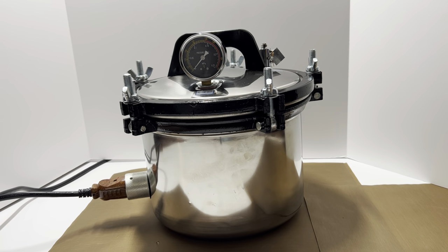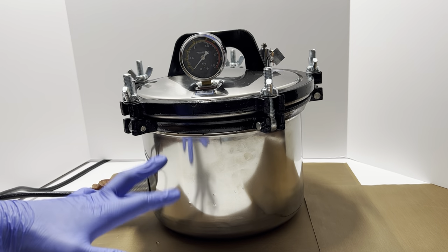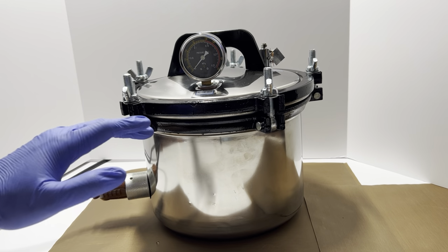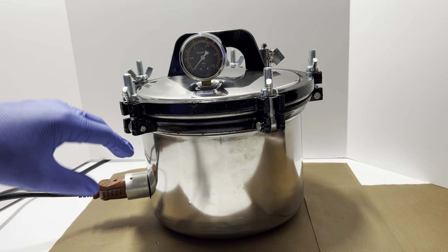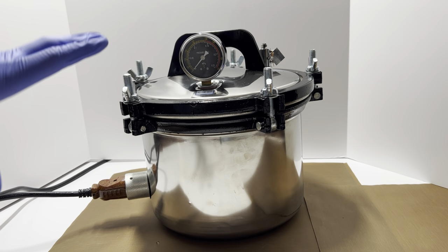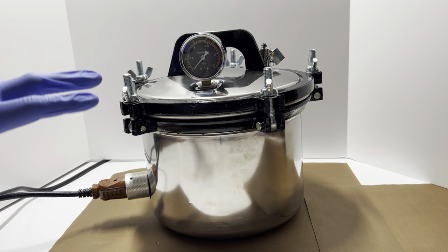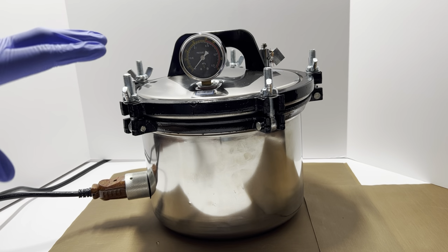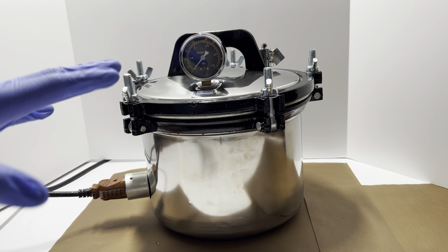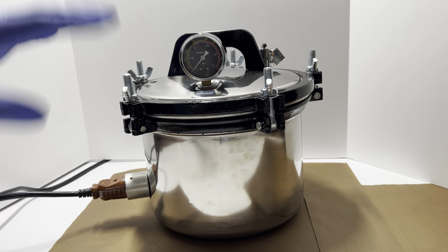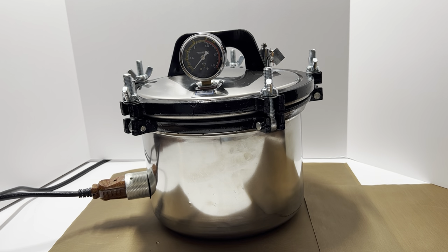So the unit is now connected to power and we can hear the water start trickling a little bit. So that's an indication that it's working, that it's heating up. I like to wait and sit around and babysit the machine. I monitor it until the process is done. I don't leave until I know that the sterilization process is complete and going smoothly. Should anything happen during the process, I'm here to monitor and pull the plug on it and cut the process short. Now, you're going to see why you need to monitor this here shortly.